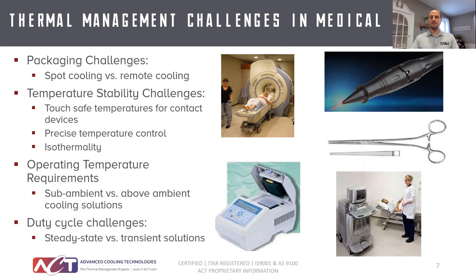The last thing we'll talk about is duty cycle challenges. Not all operation of electronics is steady state. Sometimes the operation is on and off with a relatively long off period between on cycles. If you try to cool for the steady state max peak power, your cooling solution may be way oversized for the average load of your application. We'll talk about solutions for load shaping duty cycle operation for pulsed applications and ways to address those transient thermal challenges.